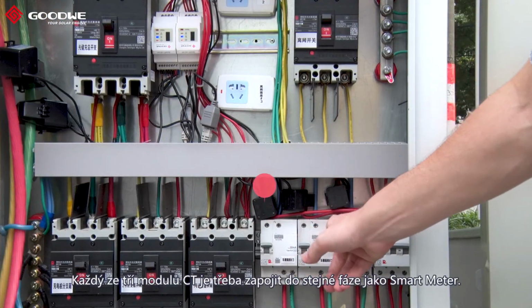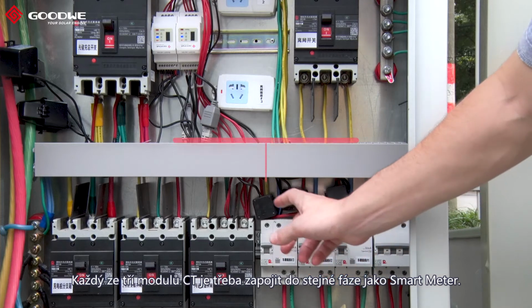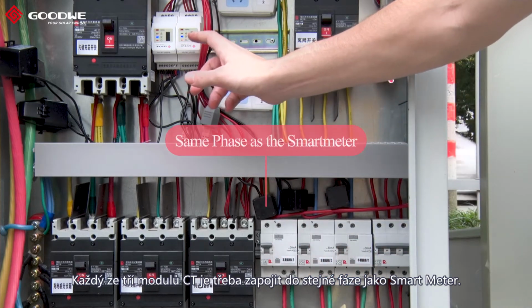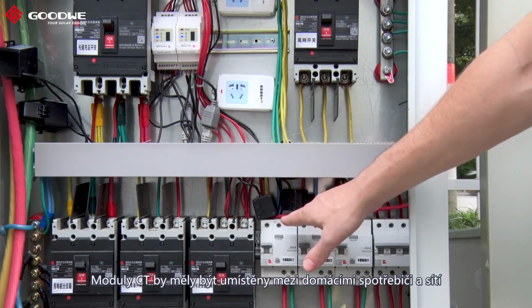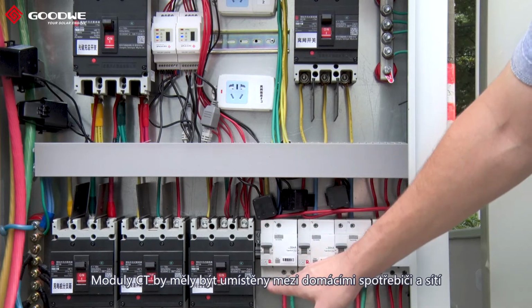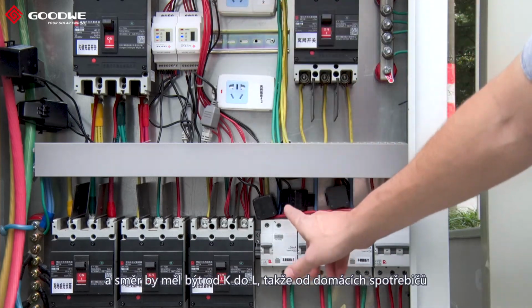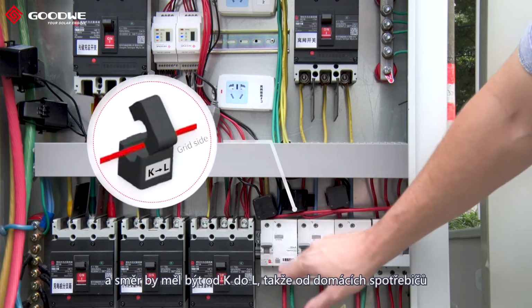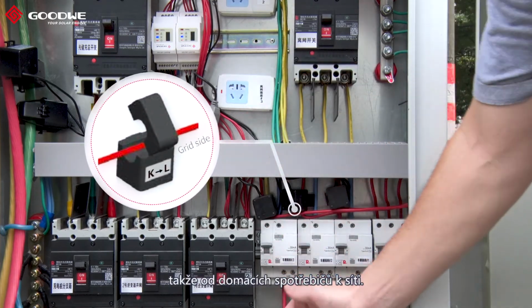There are 3 CTs, and each CT should be connected to the same phase as the smart meter. The position of the CTs should be between the house loads and the grid, and also the direction should be from K to L, so from the house loads to the grid.